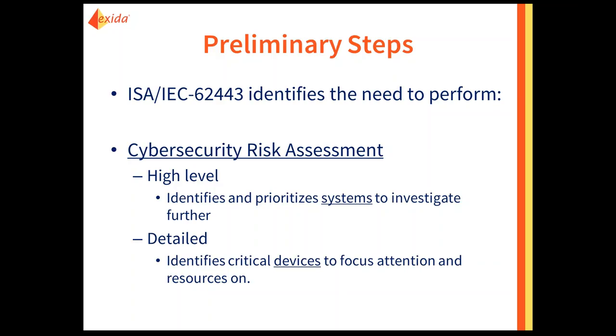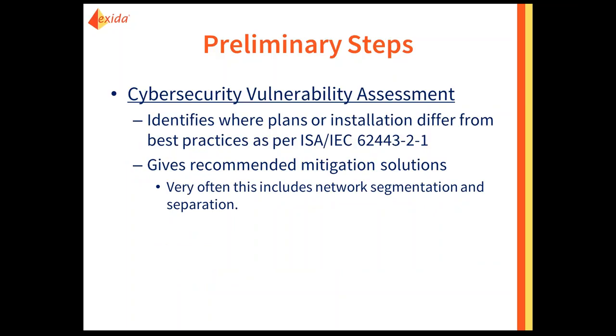The high-level assessment identifies and prioritizes the systems or functions which are either most critical to your process or most vulnerable. Once you complete the high-level assessment, you move to a detailed risk assessment, which identifies areas of the process or devices that are most vulnerable, most critical, or low-hanging fruit that can be addressed easily. Also included in the 99 series is the need for a cybersecurity vulnerability assessment.